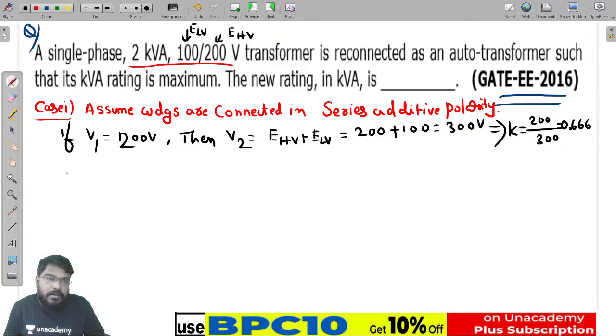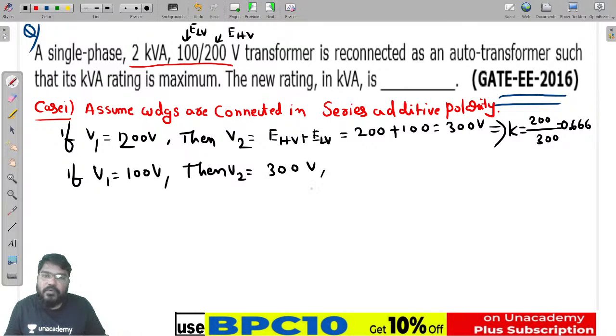This is the value of K. Next, if V1 is equal to 100 volts, there's another possibility where the windings are connected in series. Then V2 is equal to VHV plus 100, that equals 300 volts. Now let's calculate K, which is low voltage by high voltage. The low voltage here is 100, so it's 100 divided by 300, equal to 1 by 3, which is 0.33.